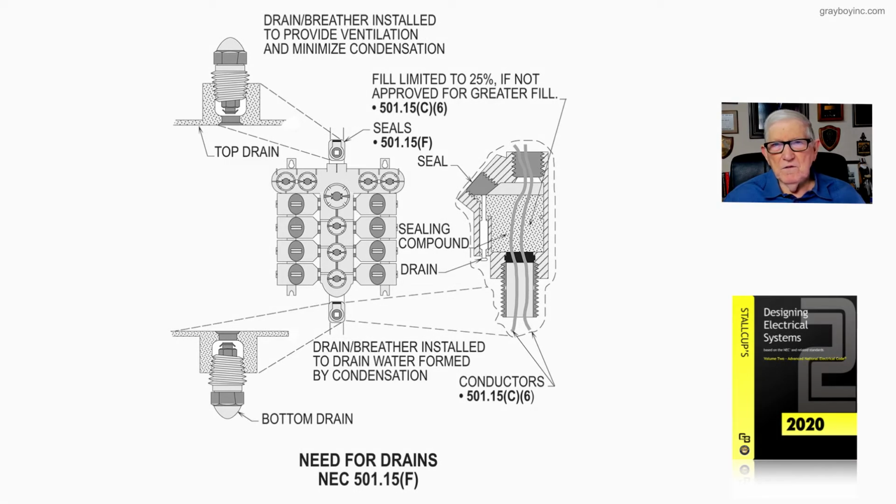Now let's look at this figure 21-38. Notice this illustration deals with the need for drains when we want to provide one. And of course, that's in accordance with NEC 501.15(F). You notice drains kind of serve as a breather installed to provide ventilation, minimize condensation, and so forth.